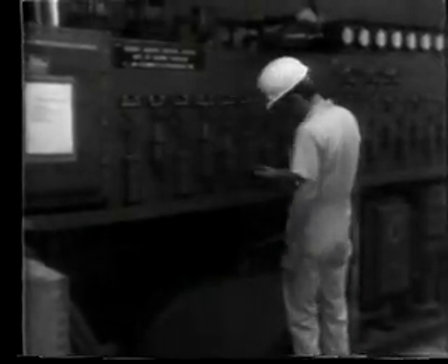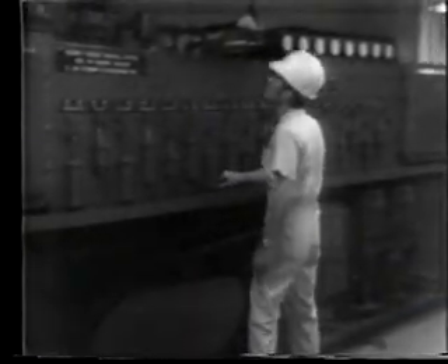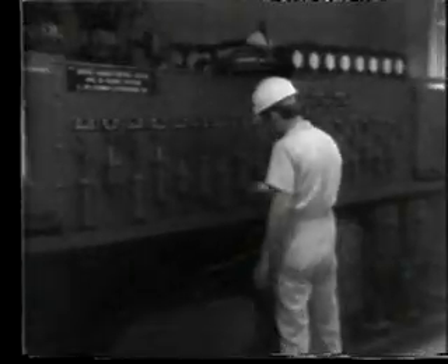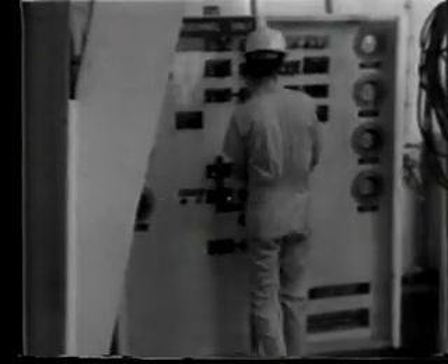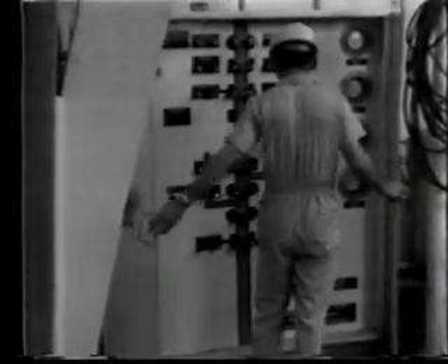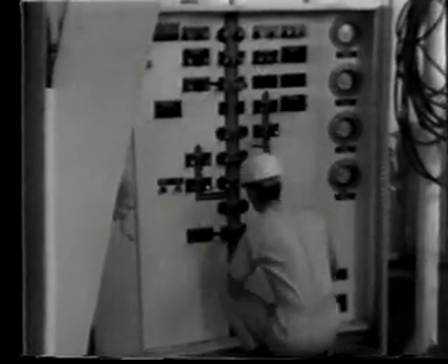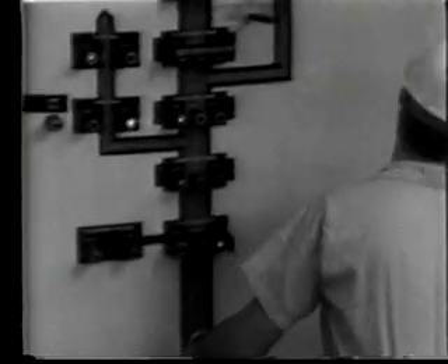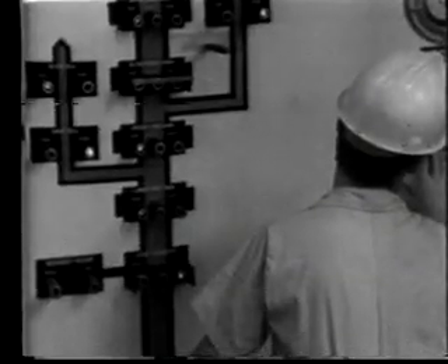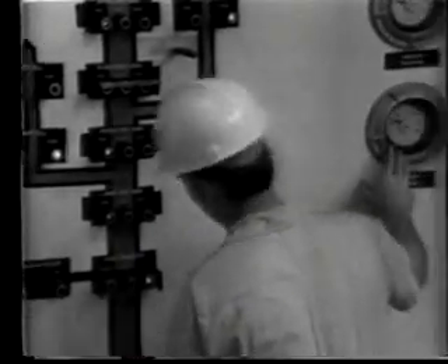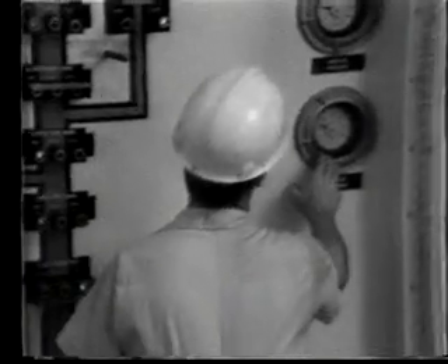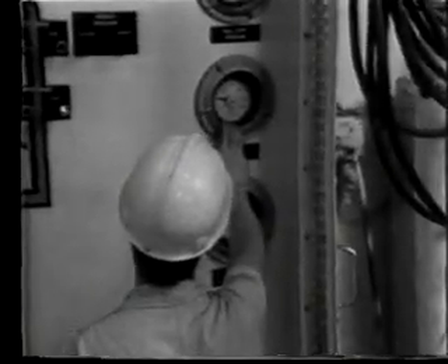If the function will not work from another panel, next you should make a mechanical check to see if you can find anything mechanically wrong with the system. This procedure is outlined in the program entitled Troubleshooting for Leaks and Malfunctions. Third, make a power check. The easiest way to tell if you have adequate power to the system is by looking at the lights on the panel. If the lights are on and are at full brightness, then you can assume there is adequate power to the system.